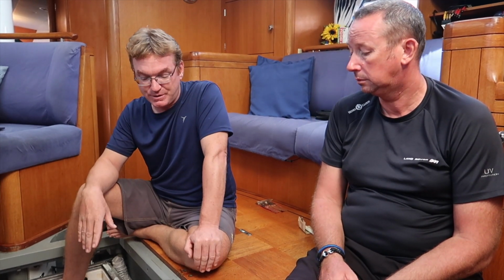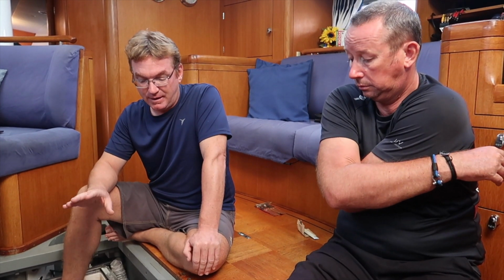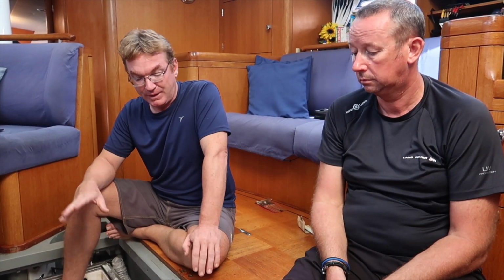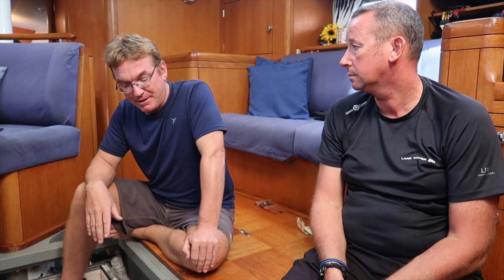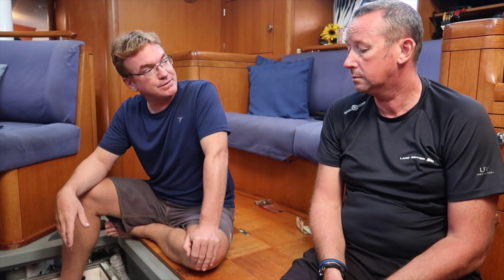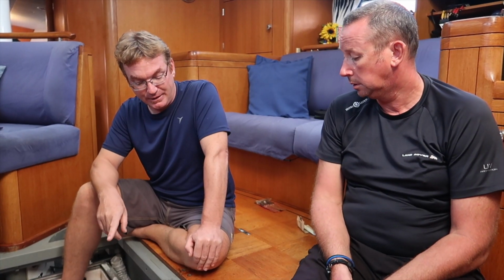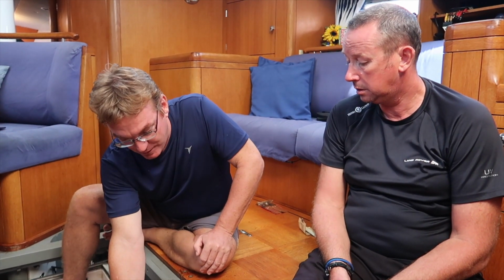Maybe once a year or so, disconnect them, because you might find one bad apple amongst the bunch that's pulling the whole bank down. It's not so common with brand new batteries, but if the bank is getting along in age, it's good to do. Also, by doing that, you'll take off all the lugs and be able to clean up all the connections, which is always a good thing to do.